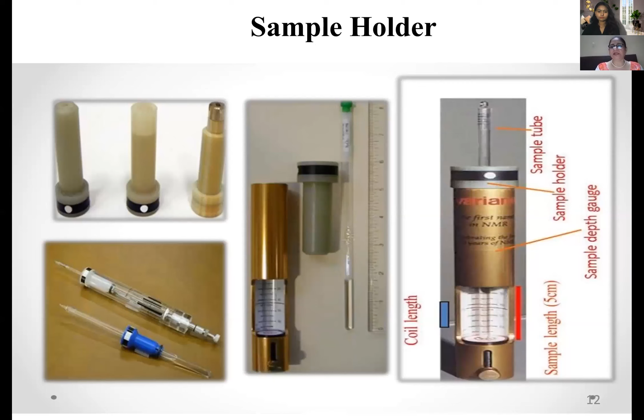This is a probe. And what exactly is a probe? The probe is very important. It is something in which you put the sample holder, and the NMR probe is the core element where the magnetic field, the radio frequency, and the sample interact with each other. It contains an air turbine to spin the sample while the signal is collected, and is used to excite and detect the magnetization in radio frequency of samples. The most essential component is the RF transmitting and receiving coil. An optimized probe configuration for the application will guarantee optimal performance. That is, different customized probes are required for different nuclei.